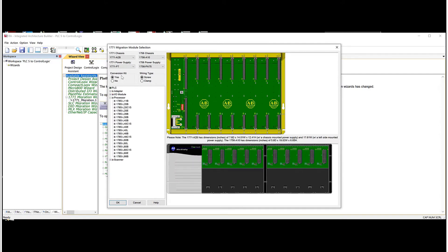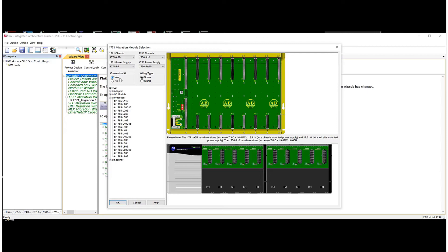Then there's a, do we want to use a conversion kit or do we want to do a straight up rip and replace? If you have the room, I highly recommend the conversion kit because what it does is it eliminates any new drilling in the panel. And also doesn't require any wires to be removed and reinserted in the new IO cards. So it saves a lot of time and it reduces the amount of labor that's required.